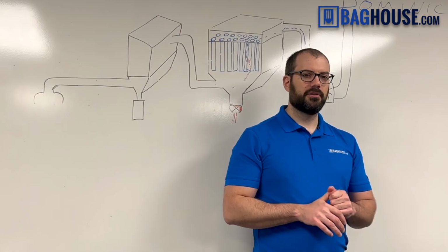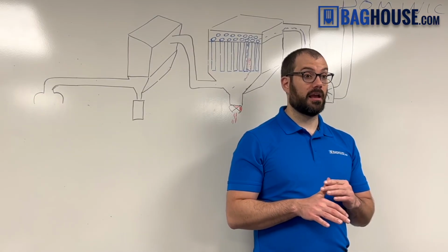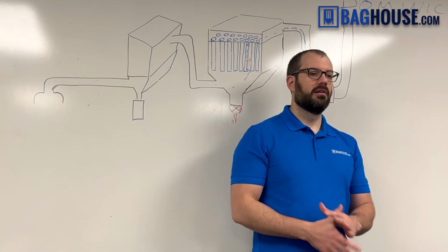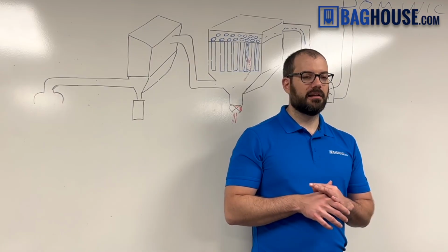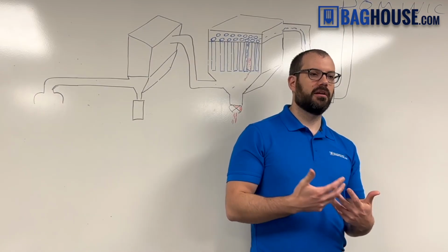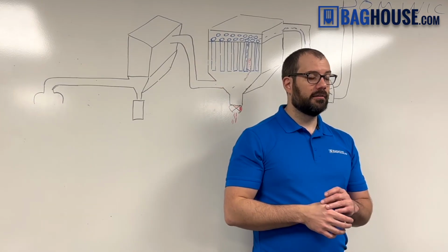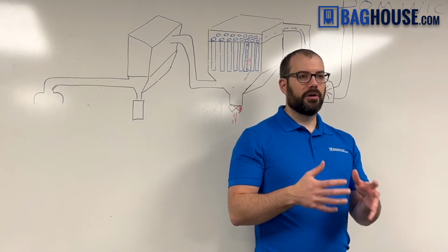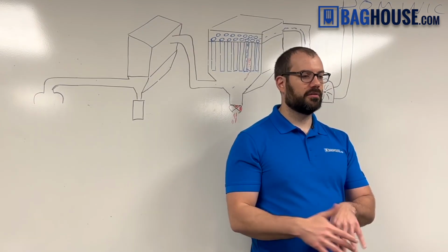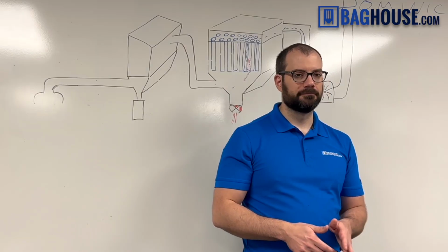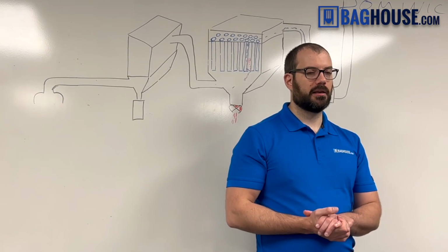We say there's low temperatures and high temperatures. So low temperature is really anything that's less than about 250 Fahrenheit. Pretty much anything under that, we just consider a low temperature kind of thing. And even if something's hot, that's fine, even if it's hotter than the ambient air outside, but nothing that has a boiler or a furnace and things like that. Anything else is pretty much, even if it creates heat, is a low temperature thing. Anything above that, we call a high temperature or a hot baghouse, okay?